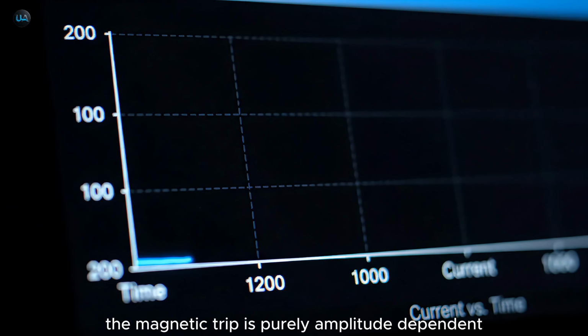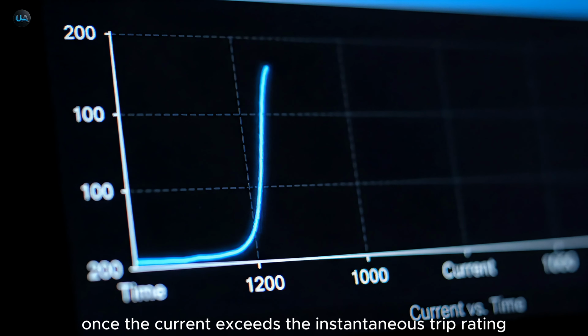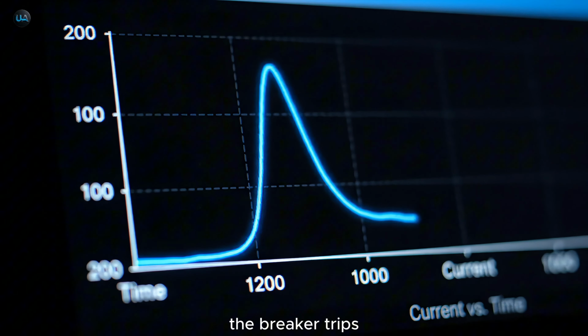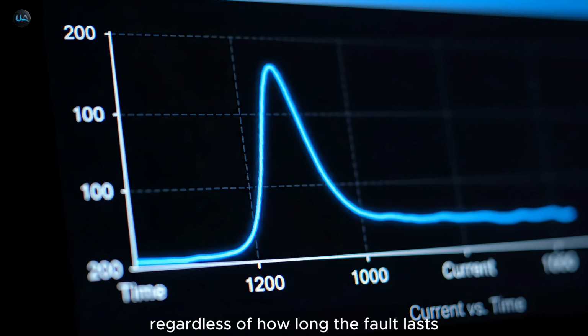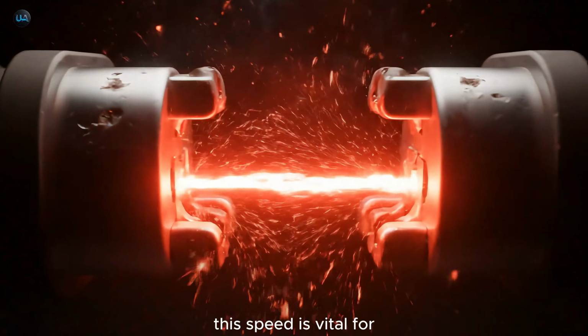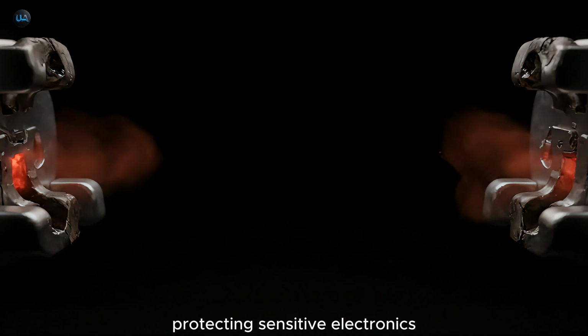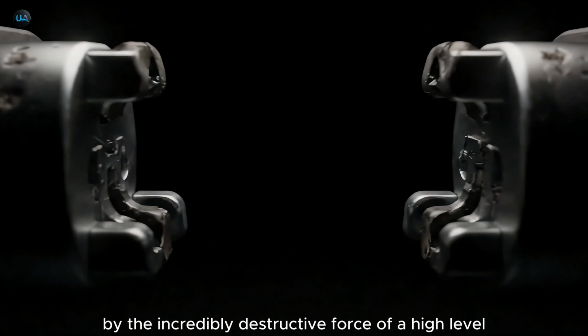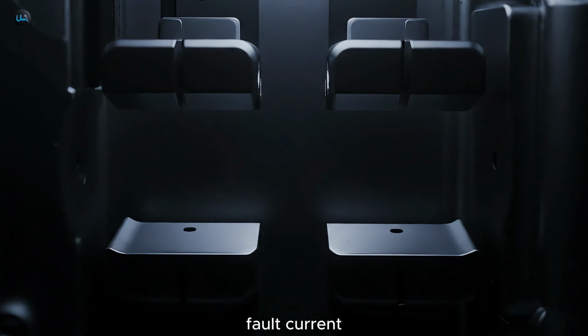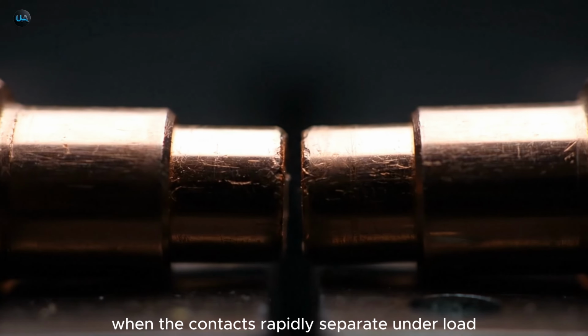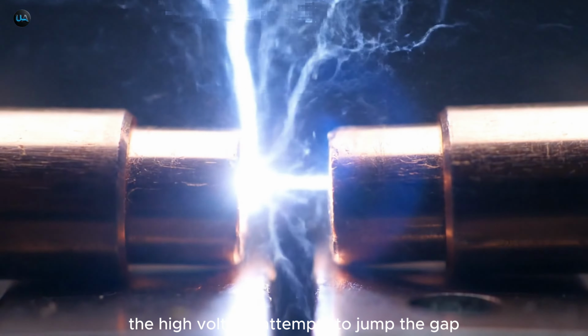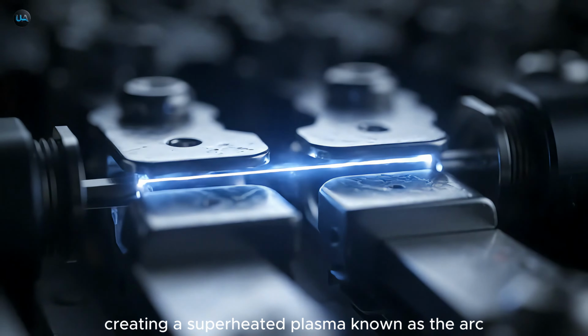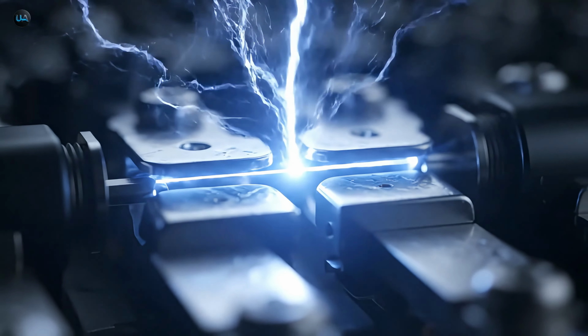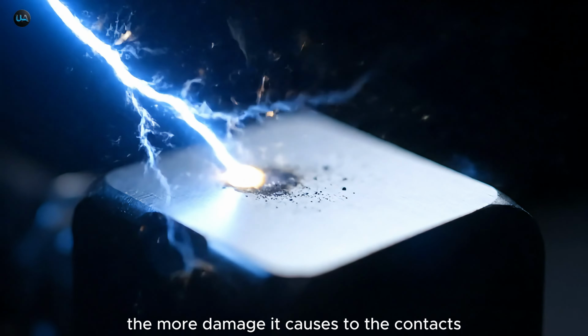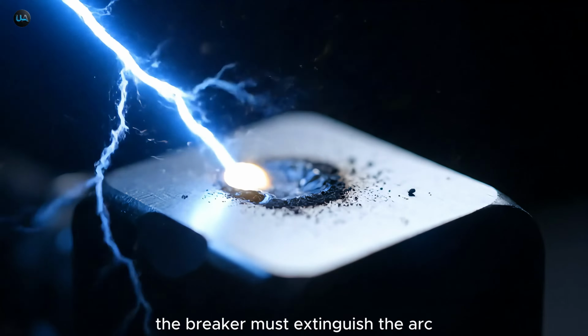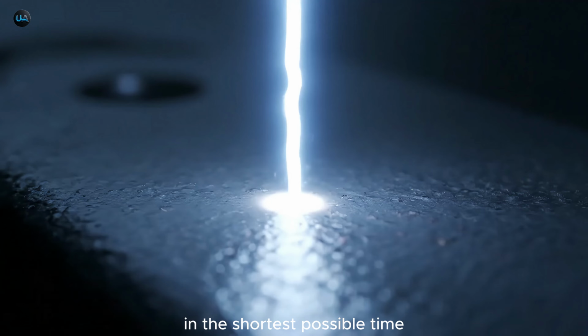The magnetic trip is purely amplitude dependent. Once the current exceeds the instantaneous trip rating, the breaker trips, regardless of how long the fault lasts. This speed is vital for protecting sensitive electronics and preventing fire or explosion caused by the incredibly destructive force of a high-level fault current. When the contacts rapidly separate under load, the high voltage attempts to jump the gap, creating a superheated plasma known as the arc. The longer this arc persists, the more damage it causes to the contacts. The breaker must extinguish the arc in the shortest possible time.